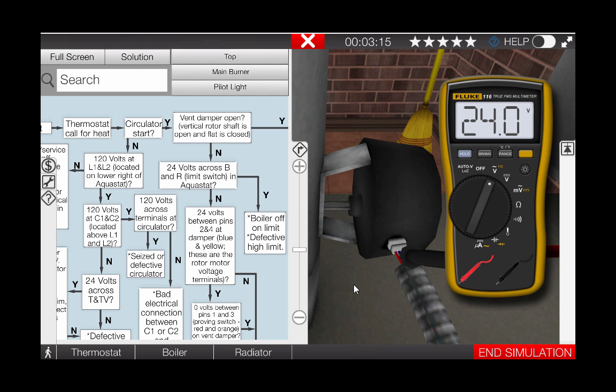Based on our reading of 24 volts, we have verified that 24 volts is present to the vent damper motor yet it is not opening. Our next step is to check the switch, or the proving switch of the vent damper.